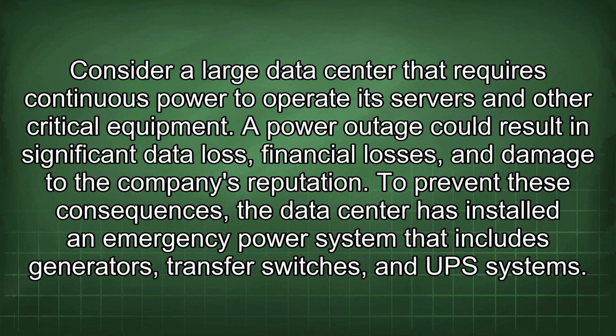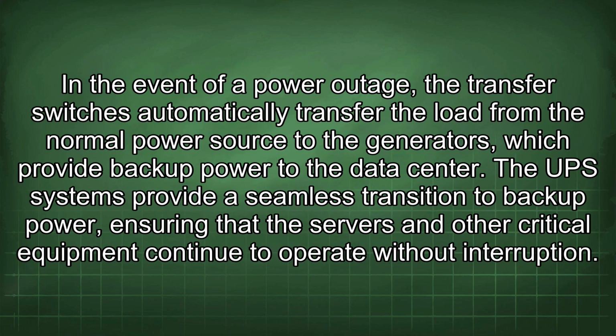Consider a large data center that requires continuous power to operate its servers and other critical equipment. A power outage could result in significant data loss, financial losses, and damage to the company's reputation. To prevent these consequences, the data center has installed an emergency power system that includes generators, transfer switches, and UPS systems. In the event of a power outage, the transfer switches automatically transfer the load from the normal power source to the generators, which provide backup power to the data center.